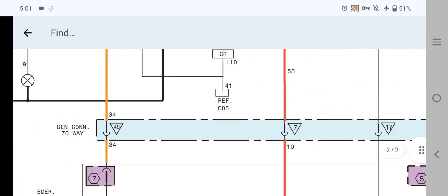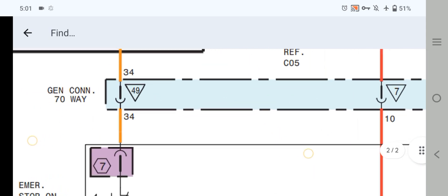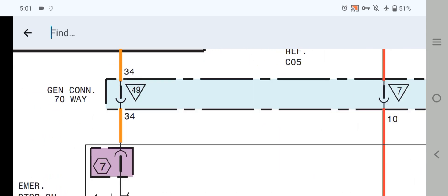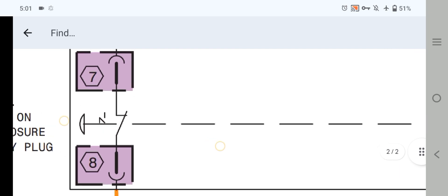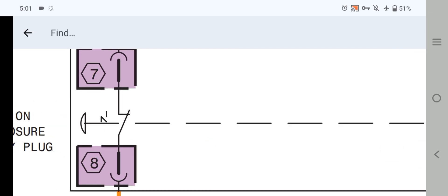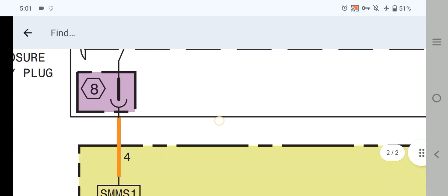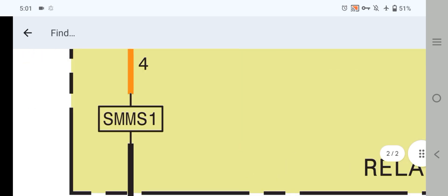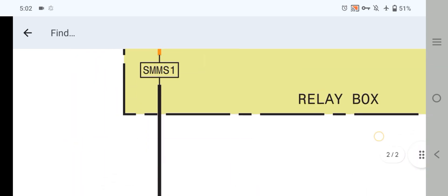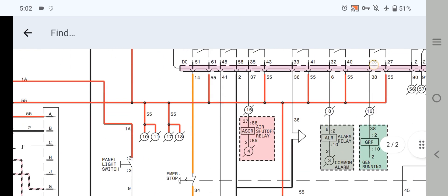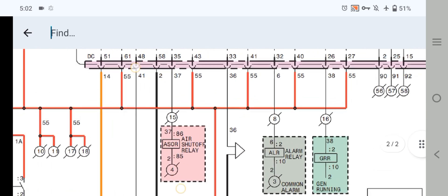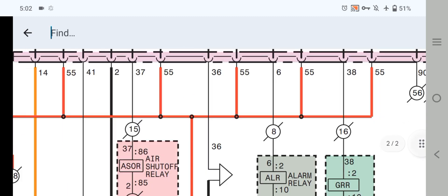As you can see, this orange wire is going to the generator 70-way connector, starting at pin 30, wire number 34, pin 49, and going out through the emergency switch NC contact, then connected to another NC contact, and then out from that NC going to the starter motor solenoid S terminal. This is all the relay circuit of the starting circuit. On the other side, the red wire, wire number 55, is fitted to all relays.